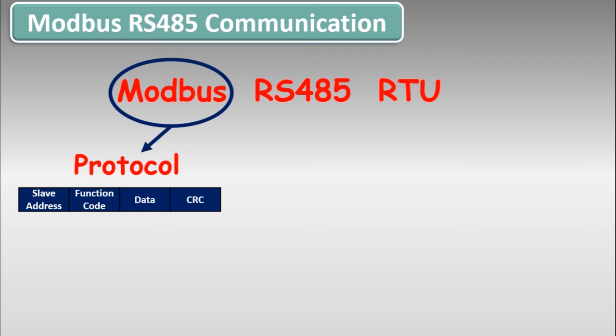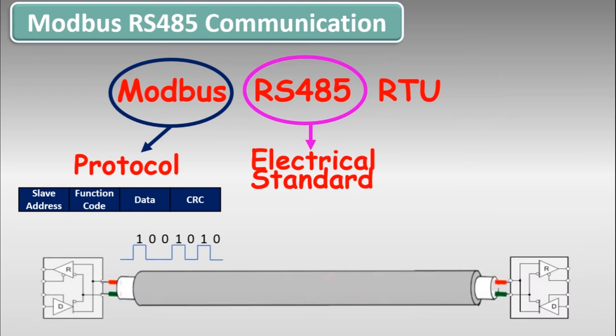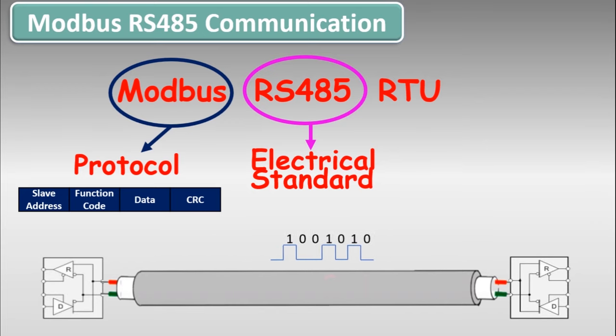Modbus protocol exists in the 7th layer of the OSI model, that is the application layer. RS485 is basically an electrical standard or a physical medium on which Modbus protocol messages move. It includes the electronic circuit, wires, and networking scheme used in the communication. In the OSI model it exists on the first two layers, that is the physical and the data link layer.